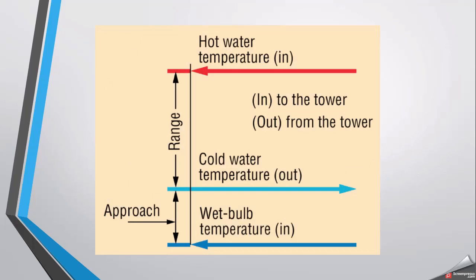This diagram illustrates the hot water temperature entering the cooling tower from a process that carries heat to be dissipated. The cold water temperature is shown going out after cooling. The difference between hot water in and cold water out is called range. The approach is the difference between the cold water outlet temperature and the wet bulb temperature of the air entering the cooling tower.